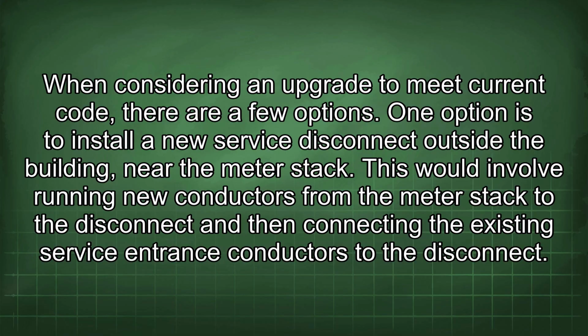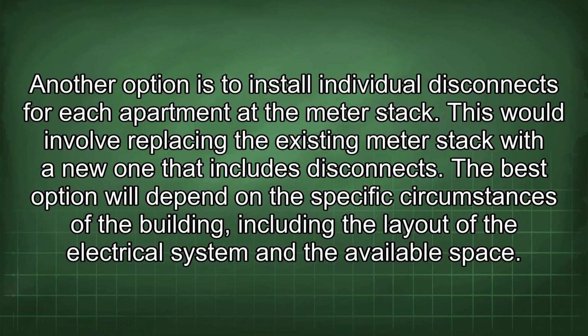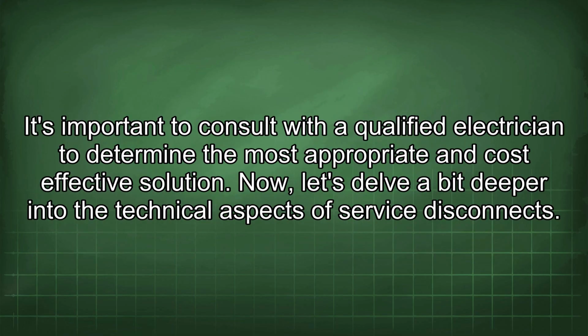One option is to install a new service disconnect outside the building, near the meter stack. This would involve running new conductors from the meter stack to the disconnect and then connecting the existing service entrance conductors to the disconnect. Another option is to install individual disconnects for each apartment at the meter stack. This would involve replacing the existing meter stack with a new one that includes disconnects. The best option will depend on the specific circumstances of the building, including the layout of the electrical system and the available space. It's important to consult with a qualified electrician to determine the most appropriate and cost-effective solution.